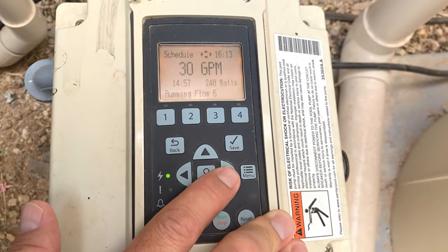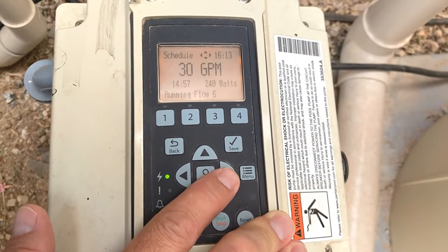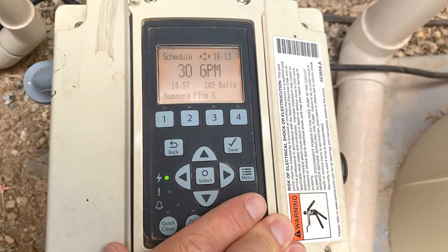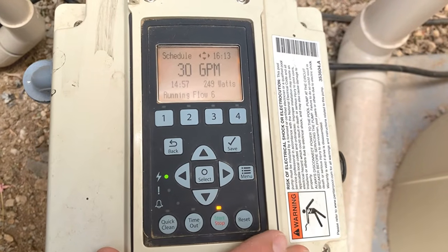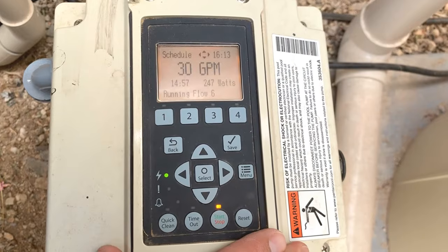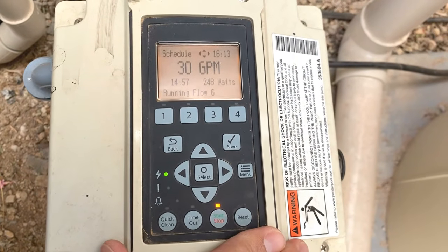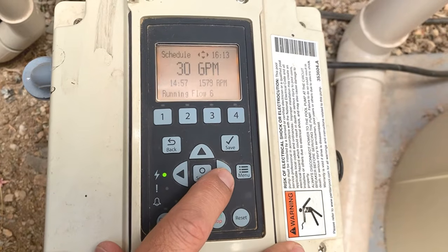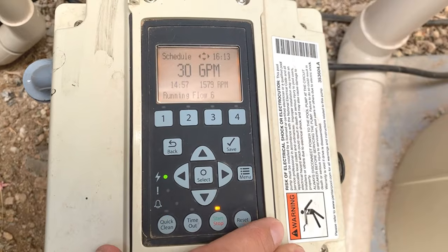I am currently pulling 248, 249 watts, as compared to your old single speed pumps that could pull 2,000 plus watts while they were running. So that is a huge energy savings for you, and part of the reason why I run this guy 24 hours a day.